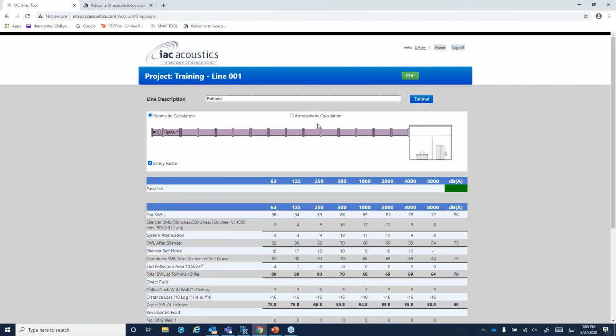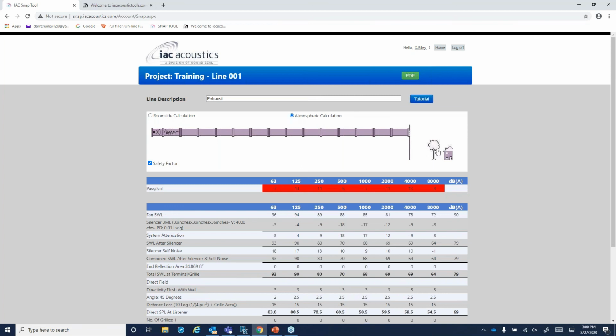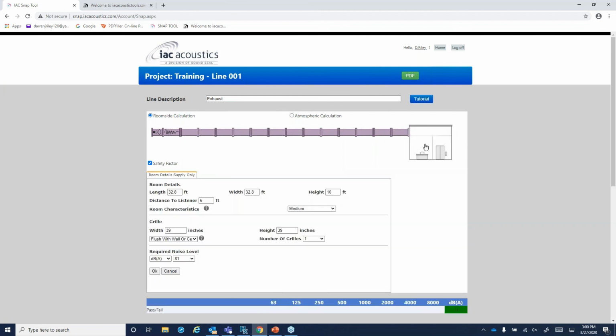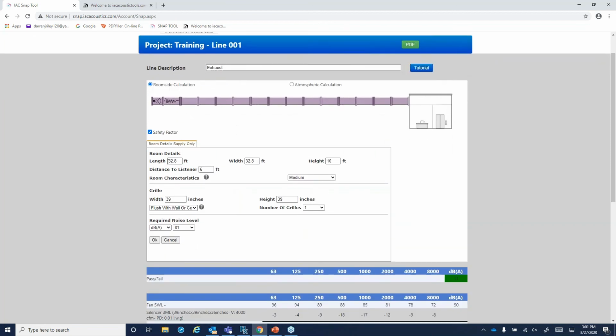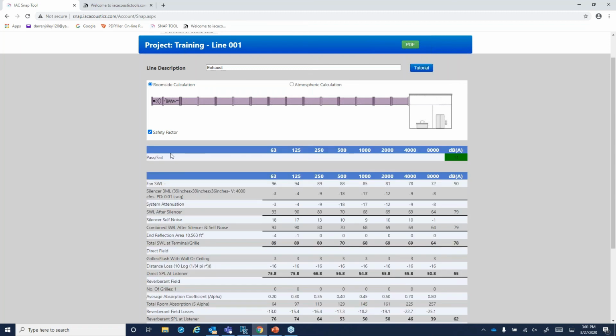You can either do a room side calculation or an atmospheric calculation outside. Click on the house and the tree, and you'll be able to change the information. Same thing with the room. You can click on the little room there. You see this is the information that is defaulted. I have changed this, and instead of an NC rating, I have gone to a dB rating at 81. For the example that we're going to use, this is what is needed. The grill width and height will be the same as the duct and or silencer for the snap tool. Click OK. What you've done is set the room parameters within the tool.